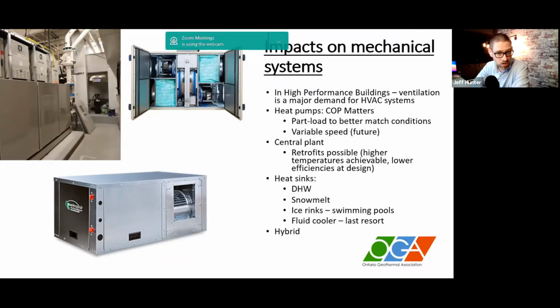Now we need to talk about heat recovery and even total energy recovery systems, because of the energy that we put into, first of all, heating the space, we want to recover as much of that as possible, and we don't want to reject that to atmosphere. But also the energy on the cooling side, both for dehumidification as well. So if we've dehumidified the air through cooling energy, we want to recapture that, and we don't want to be introducing more humidity than we need to. So the difference between a standard performance heat recovery ventilator and an energy recovery ventilator that is passive house rated, that can give you an effectiveness of 85% or greater, the differences in effectiveness there will have a long-term impact on the performance of the ground loop.